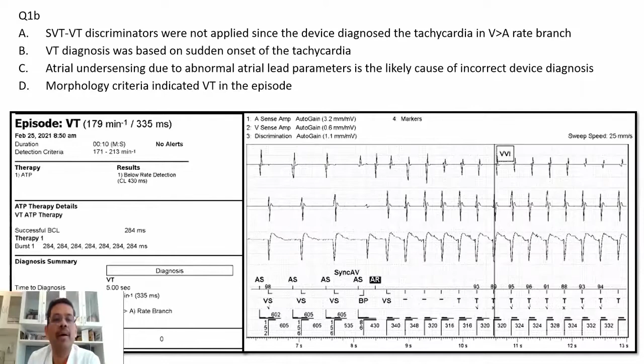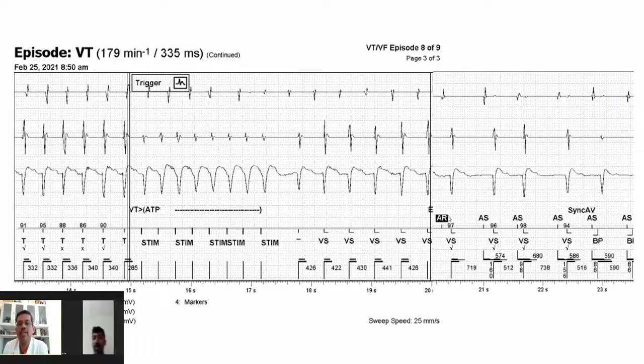So if you look at this again, the same thing, it says VT more than A rate branch, and the device then went on to deliver ATP therapy, where this is the ATP delivery. After the ATP, the tachycardia terminated, and during VVI pacing during the episode, you see only VS markers, and E, which is the end of the episode, which was previously called return of sinus in the Abbott devices, happens, and then it is followed by a sync AV algorithm coming into picture, followed by biventricular pacing.